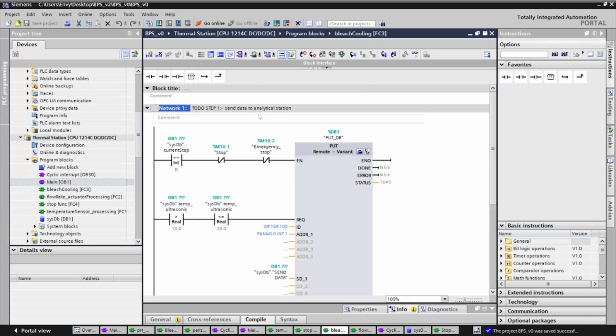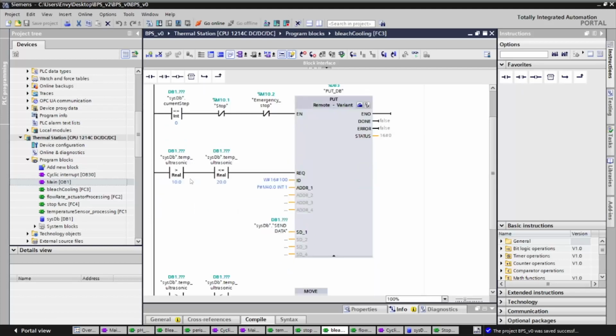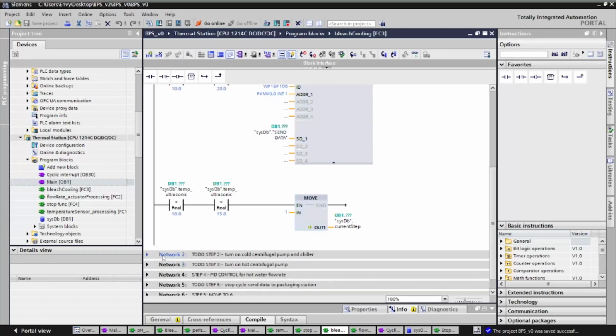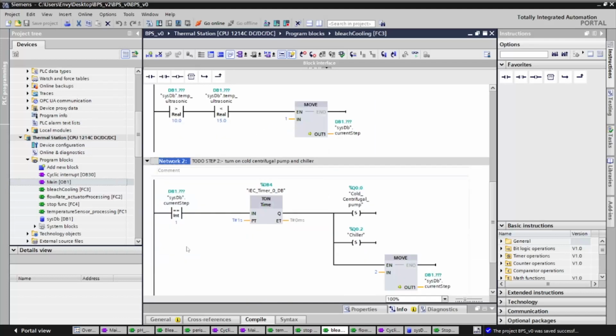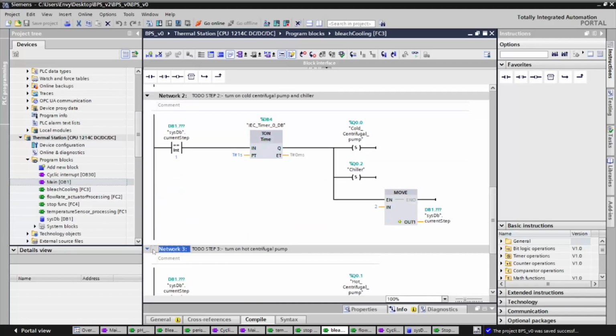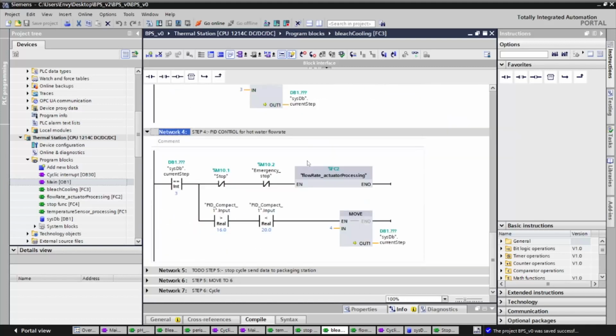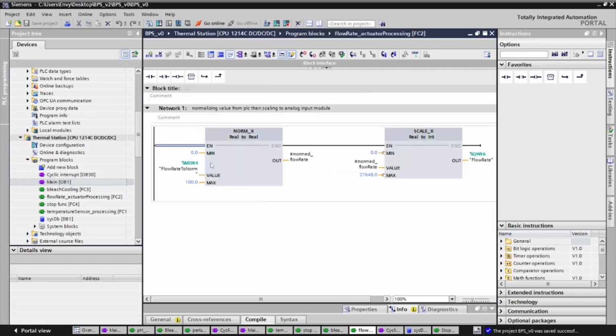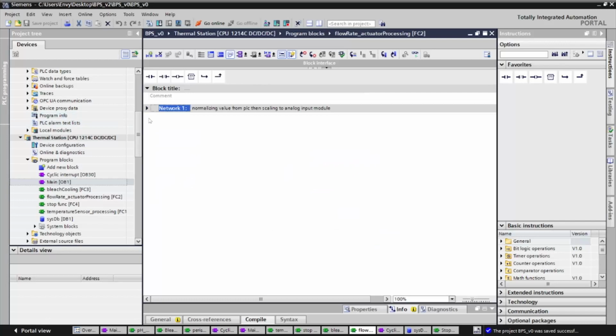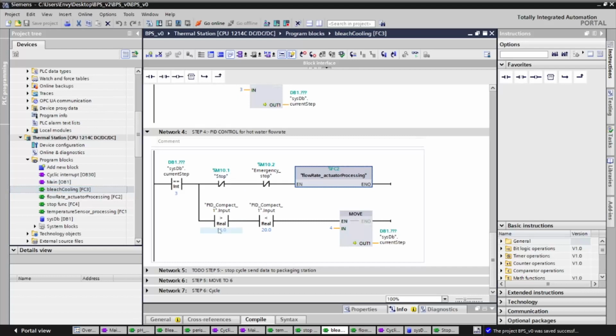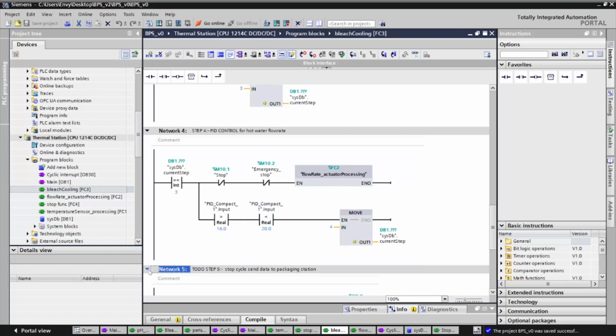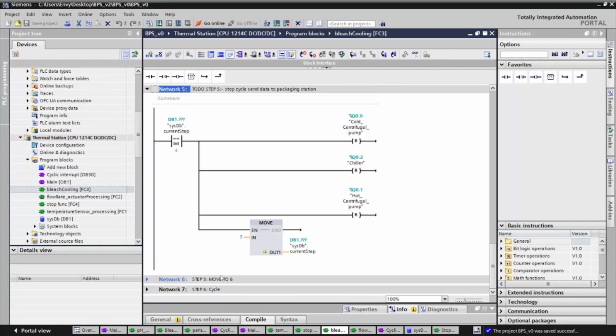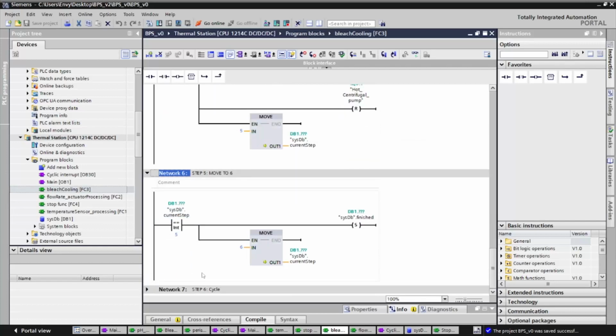On the first network, we send information to the PLC on the analytical station to say the level of the process tank, as once it's been reached or filled, to stop the transfer of the bleach. Then we turn on the centrifugal pump that circulates the bleach to the chiller, which we also turn on. And we have a hot centrifugal pump that circulates warm water, which we regulate the flow rate of in case the temperature of the bleach goes below the required one. When the temperature is below 16, the PID will be called, and once that's done, we'll stop the circulation. To indicate, this network indicates the system is finished.